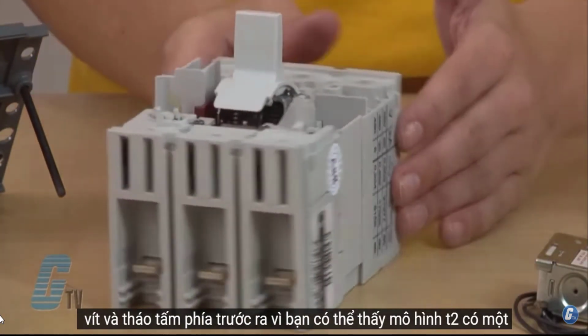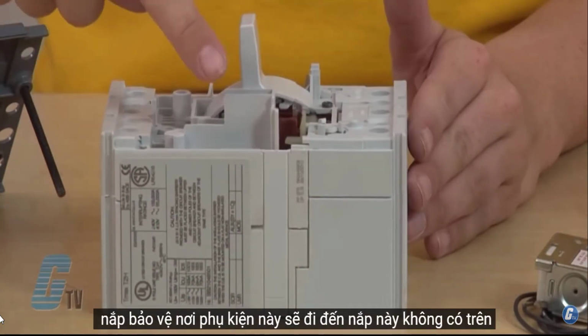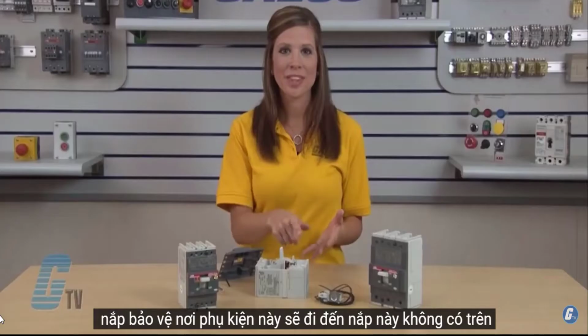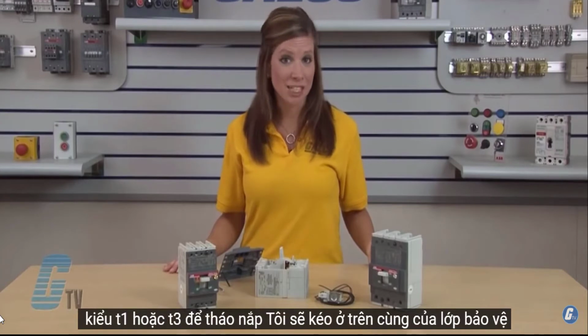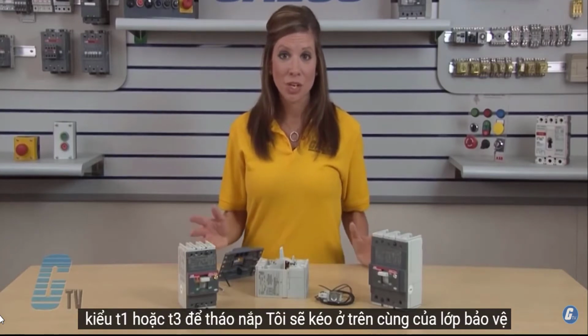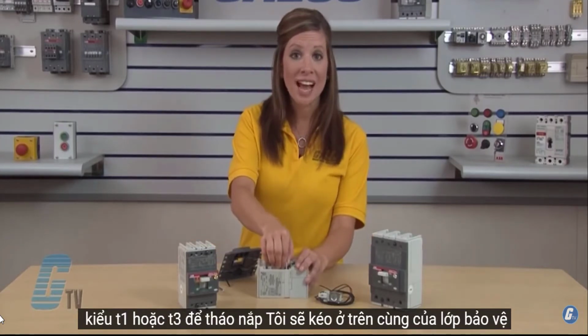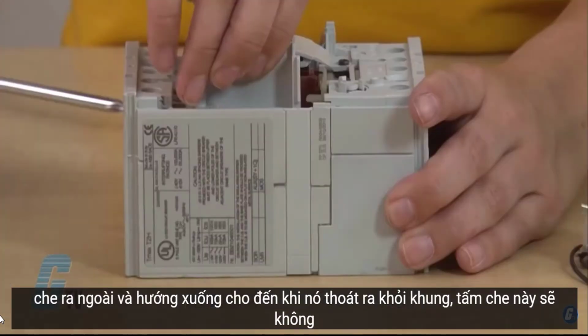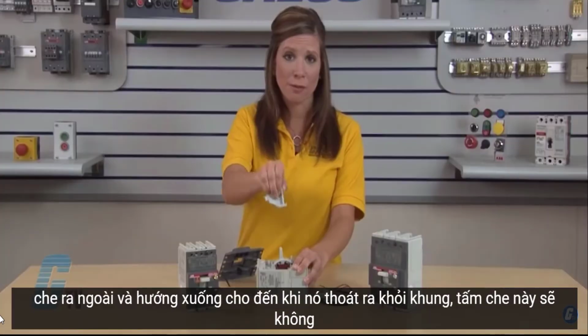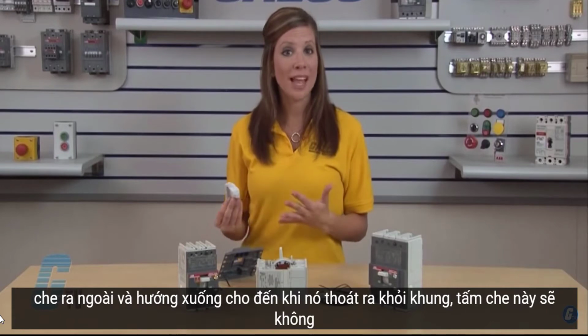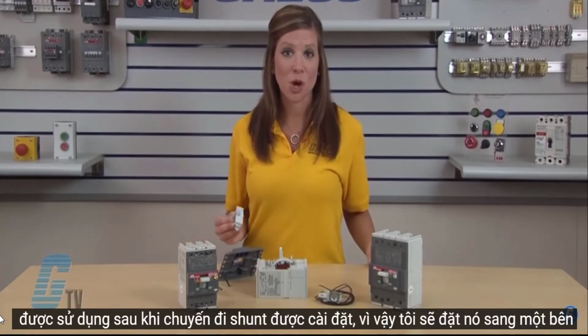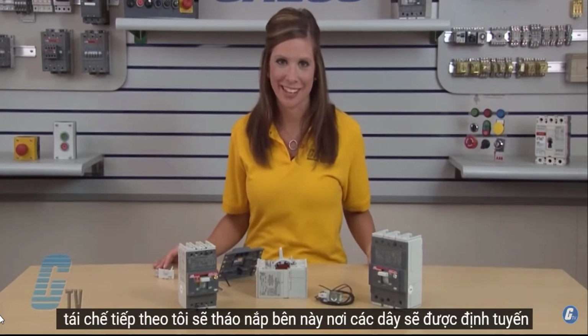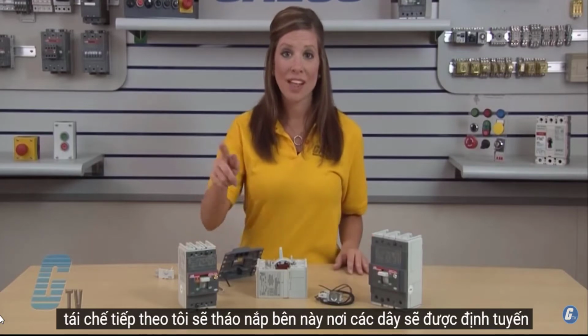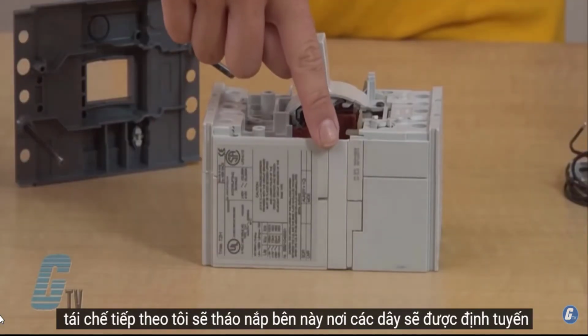As you can see, the T2 model has a protective cover where this accessory will go. This cover is not present on the T1 or T3 models. To remove the cover, I will pull on the top of the protective cover outward and downward until it is free from the frame. This cover will not be used after the shunt trip is installed, so I will set it aside for recycling. Next, I will remove this side cover where the wires will be routed.